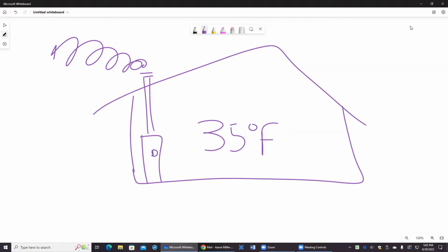But when the 15 minutes is over, you either have to push the button again or the heat goes back to 35. And then we have an outdoor lockout that if it's above 35, the heat won't come on. So outdoor lockout 35, keep the warehouse 35, and we're going to save some fuel. If it goes above freezing outside, then there's no possible way the building could freeze because the building would pick up heat. It'd be warmer than 35. So that's what we're going to do.